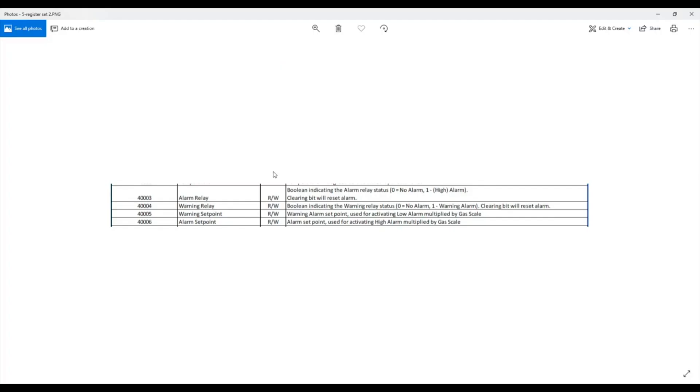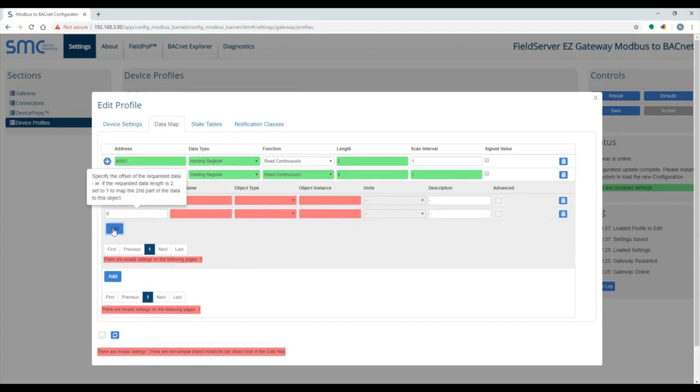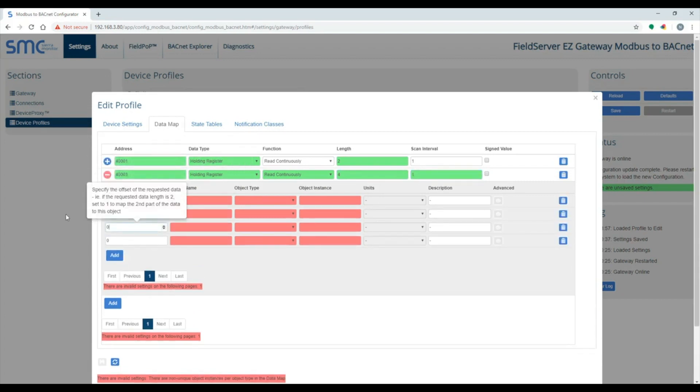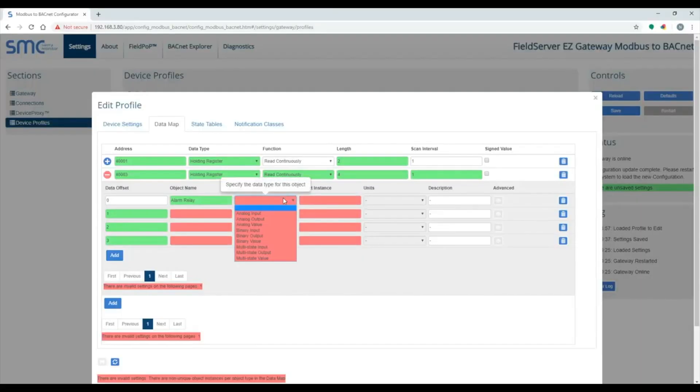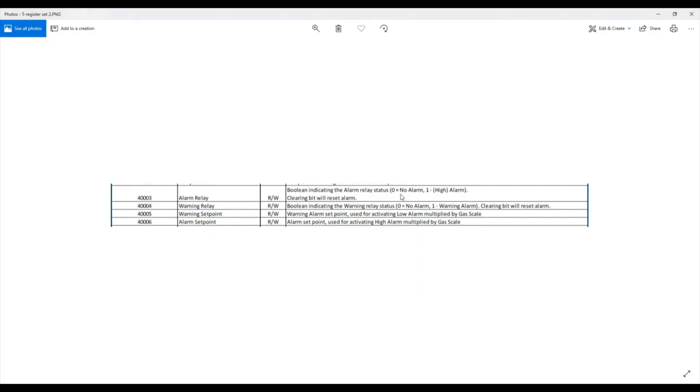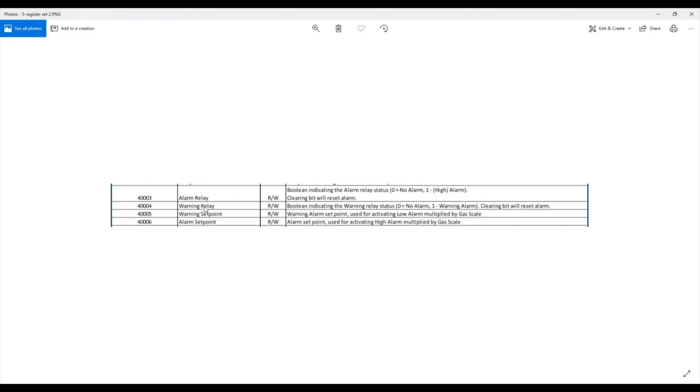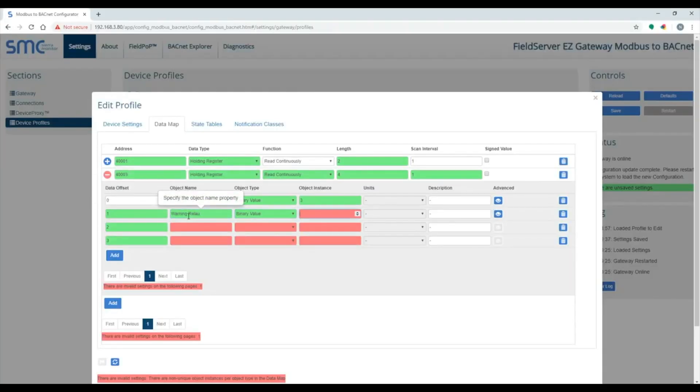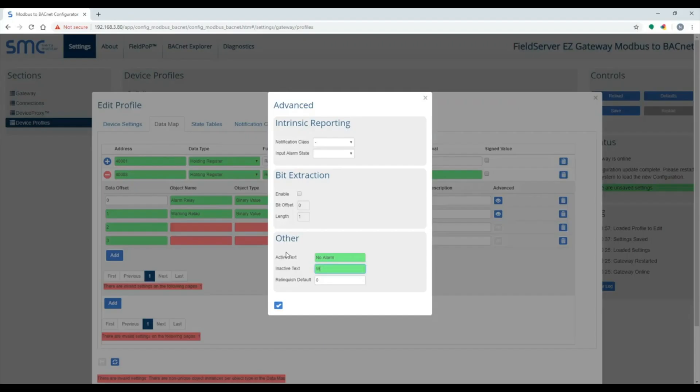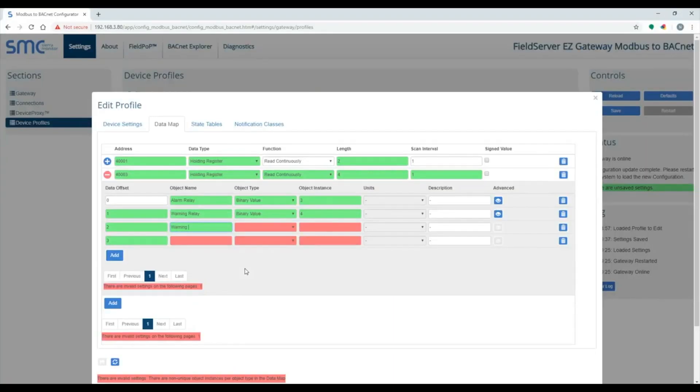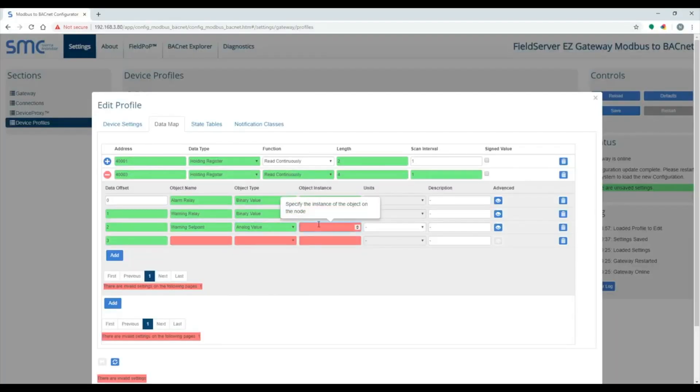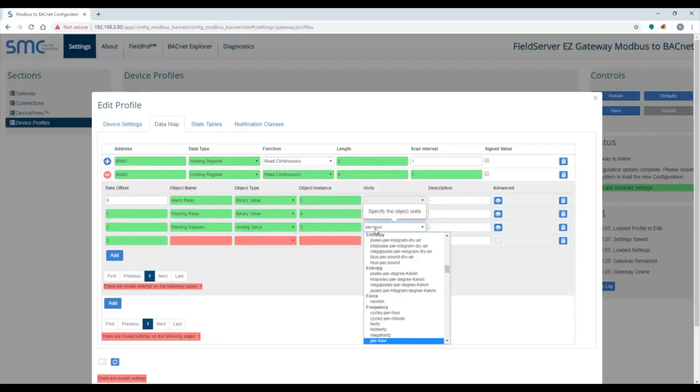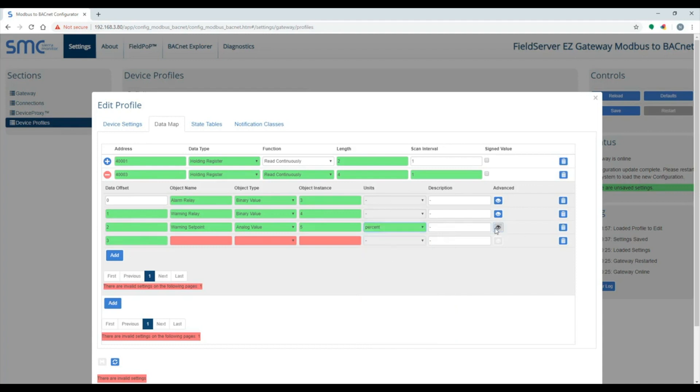The next block of registers is 40003 through 40006. Four consecutive registers. Put length 4, so you have data offset 0 through 3 to work with. These are writable points, so make sure to use a writable object type. You can specify inactive and active text for the binary points. Warning setpoint uses the same scaling as the concentration, along with the alarm setpoint.